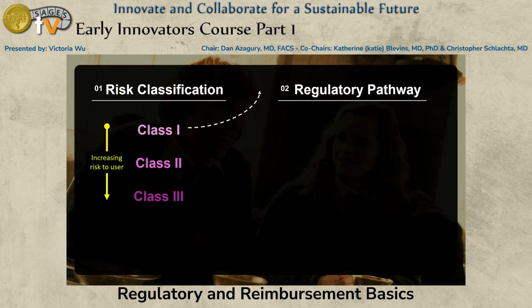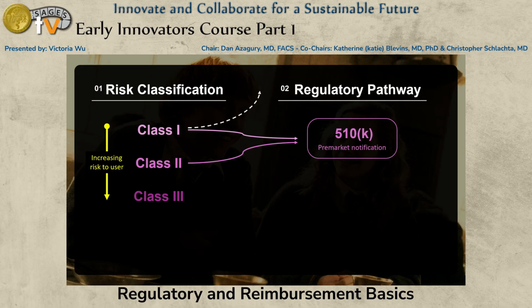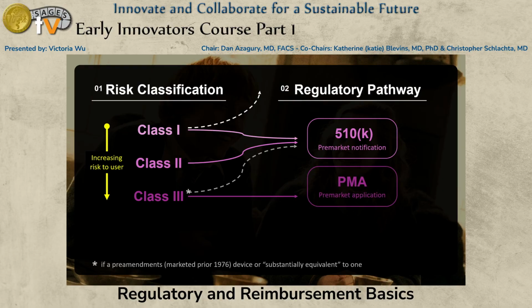So we saw that some class 1 devices are completely exempt from this regulatory pathway business. Then the majority of class 1 and 2 products go through the 510K pathway, and then class 3 go through the PMA pathway. There are some exceptions, but in general, the difference is that you're required to include more controls in the design of the product, and there's a lot more requirements in the application itself for a PMA.